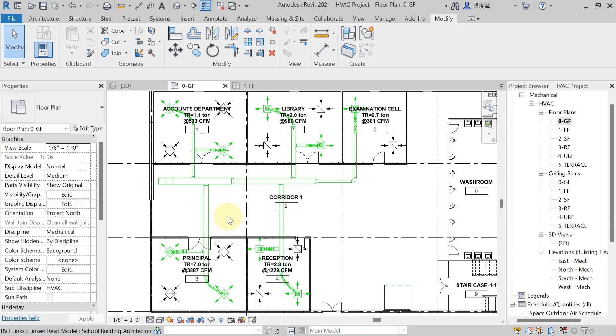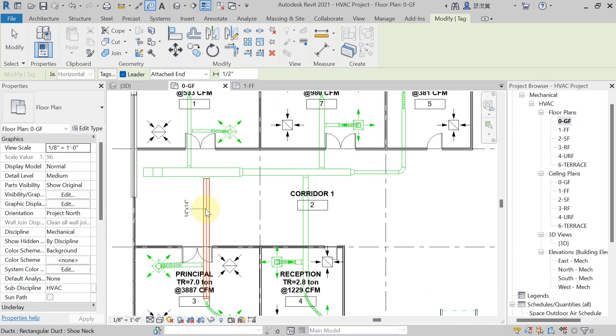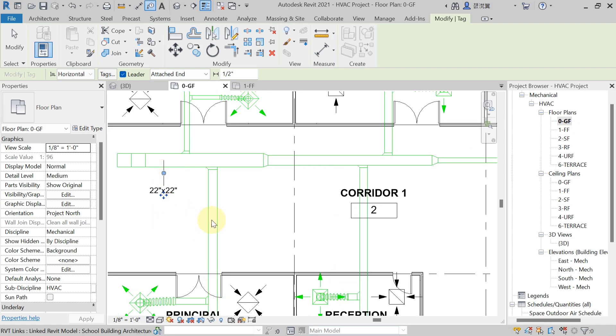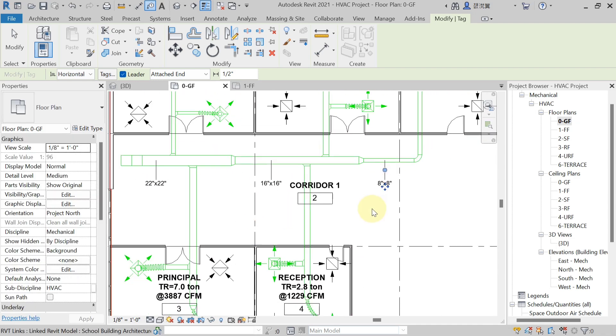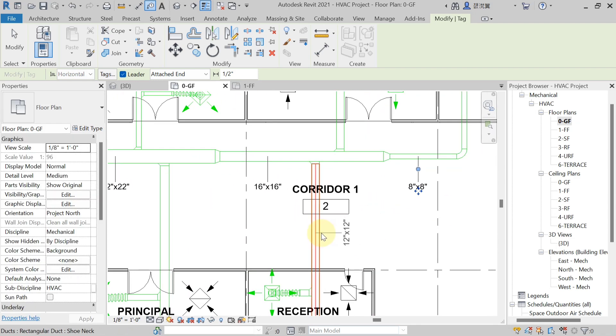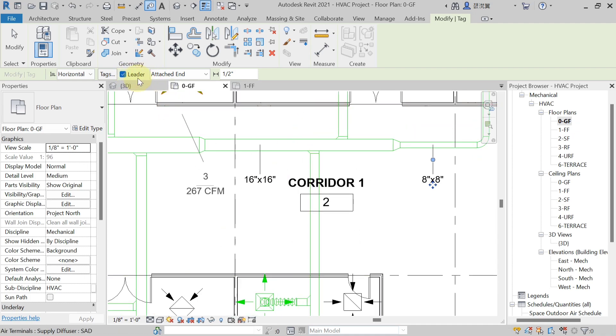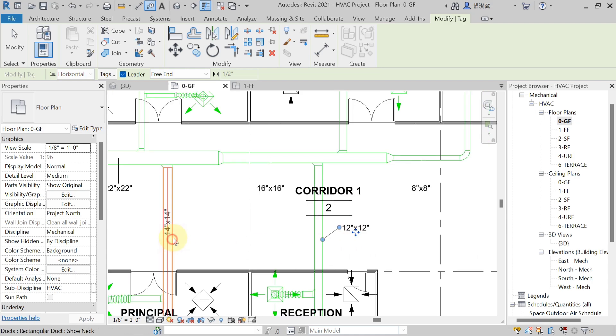Just use the shortcut TG — press TG and move the mouse near to the ducts. It is showing you the size: 14 inch by 14 inch. The main duct size is 22 inch by 22 inch; after reducing, the size is 16 inch, then after reducing further it is 8 inch by 8 inch. The branch duct size is 12 inch by 12 inch. You can attach the tag or set it as a free end as per your requirement.